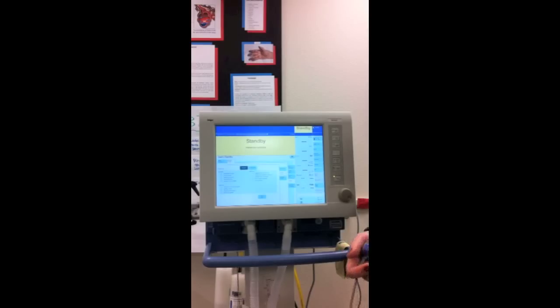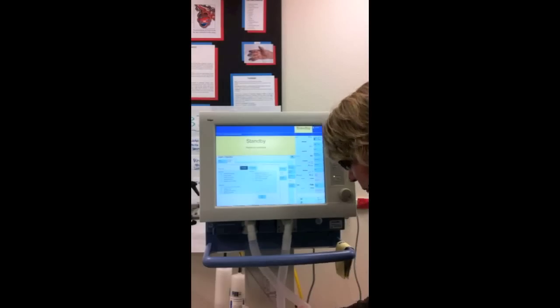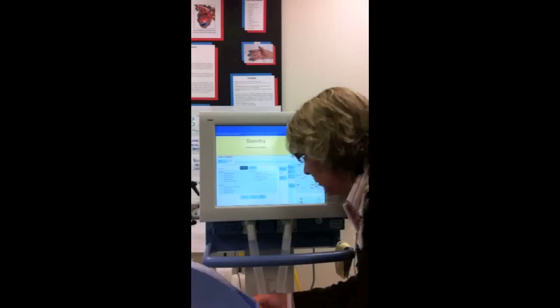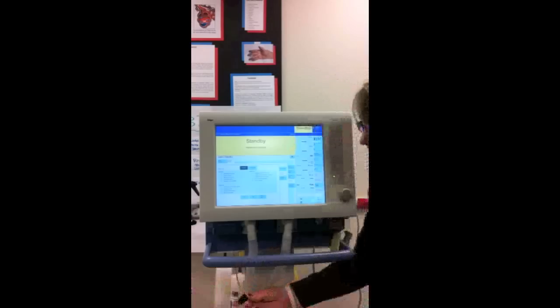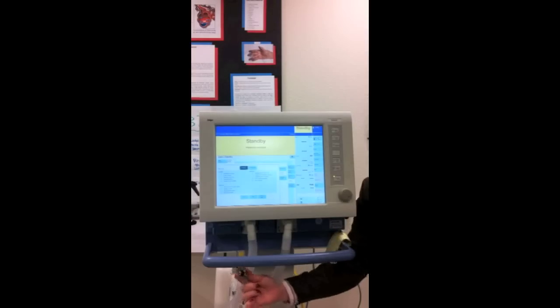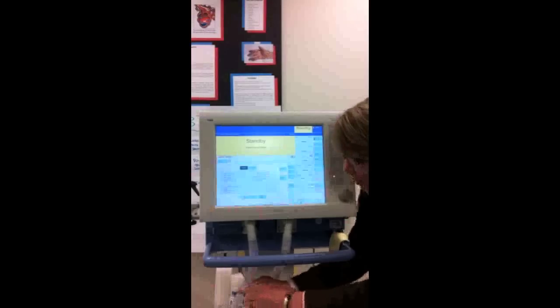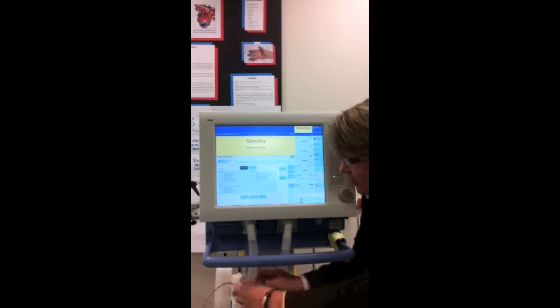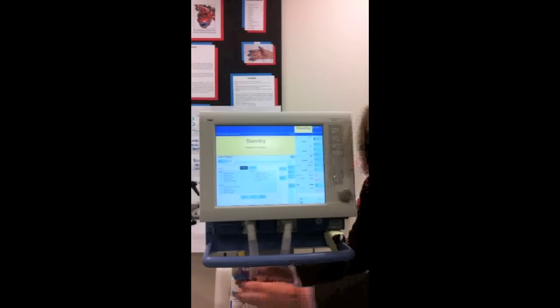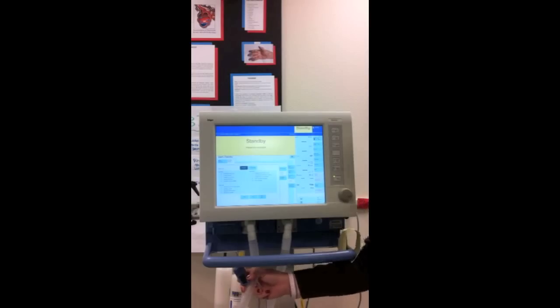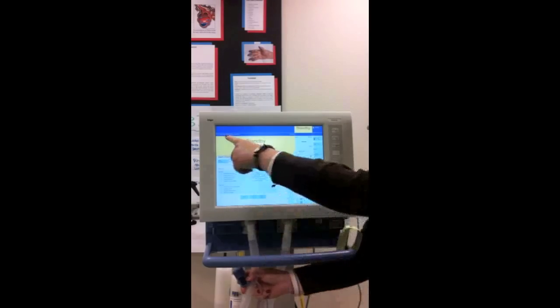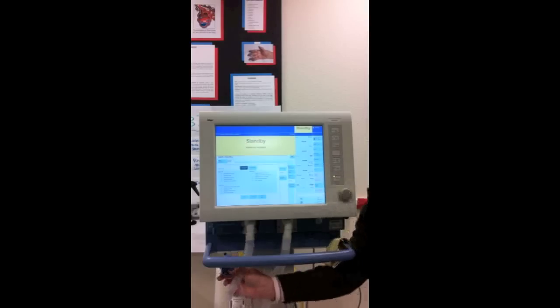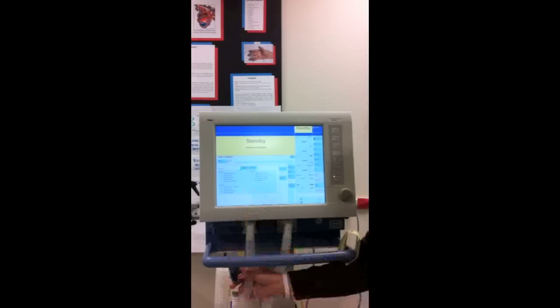Normally they have, there it is. Yeah. So the CO2 sensors usually have this on there of some sort. So down here it is. When you're going to put it for calibration, you put that in place like that, slide it in there, and see it says CO2 sensor fitted into cuvette. So yes, it's in there right now, and we're going to say yes.